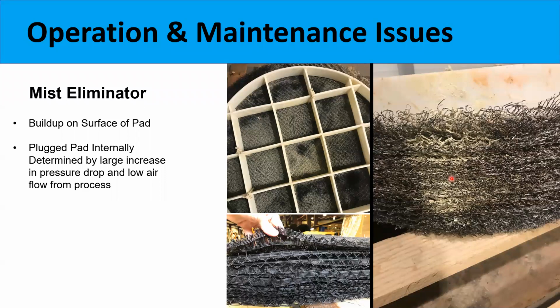One issue that we see a lot in composite mesh pads is that they'll get built up, they'll clog much more easily than a chevron vane style mist eliminator. And so in this case, you have a surface buildup that's beginning on the pad, and then it's worked its way into the cross section of the pad, ultimately causing that pad to plug, increasing the pressure drop across that mesh pad and reducing overall airflow in that scrubber system.